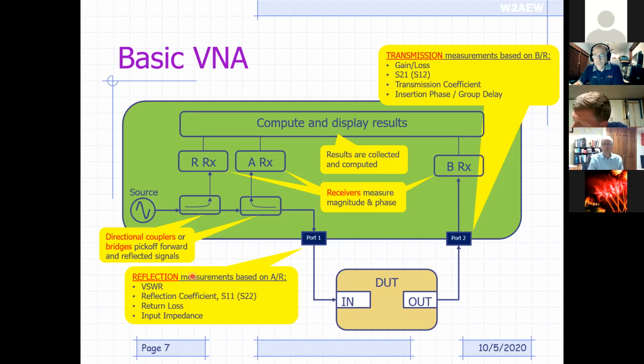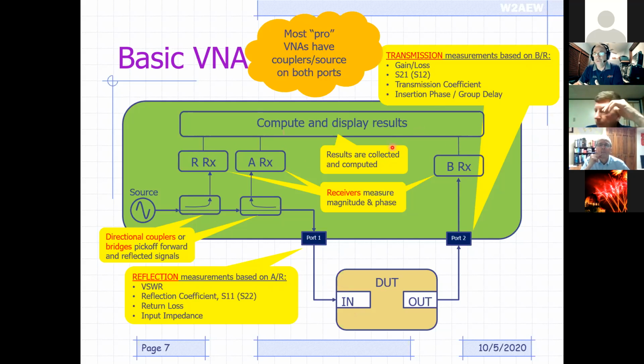And if you look at these carefully, the reflection measurements are based on this ratio, the measurement made in the A receiver as compared to the R receiver, so A over R, where the transmission properties are the measurements made in the B receiver with respect to R, so that's B over R. So that's where all the math and computations happen, just by taking A over R for the reflection properties and B over R for the transmission properties. Now, most professional VNAs, not these little nano VNAs that we got here to play with, will have a source and couplers on the other port as well, because then they can measure reflection properties at the output of a DUT, as well as measuring reverse transmission or isolation measurements. Okay, so that would give rise to S22 and S12 measurements, as opposed to the S11 and S21 measurements.